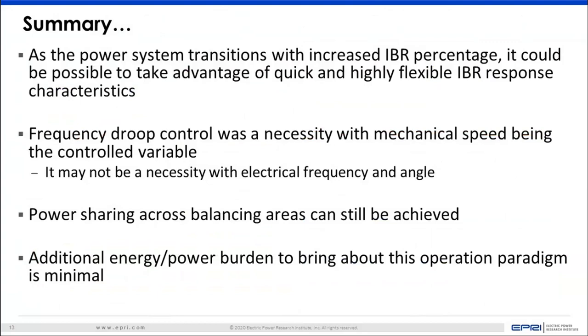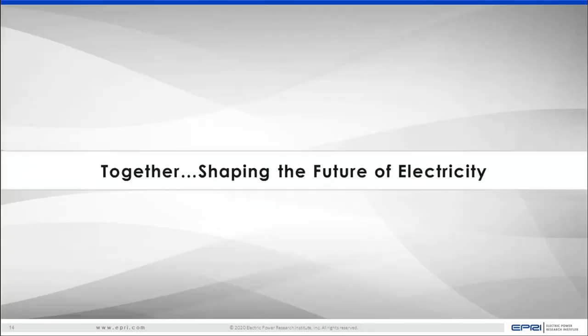So I just want to summarize with the fact that we have been accustomed to frequency Droop control, which was a necessity because of the mechanical speed and mechanical variables involved with rotating machines. But as we go to a system which has more inverter-based resources, with minimal additional energy we could probably get much more superior frequency control and achieve a tighter controlled system in this new paradigm. So, Julia, that's about all I had.